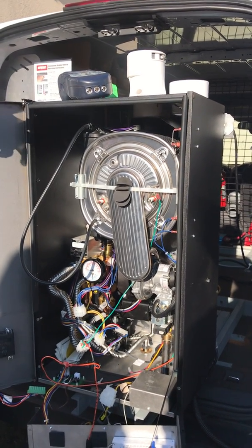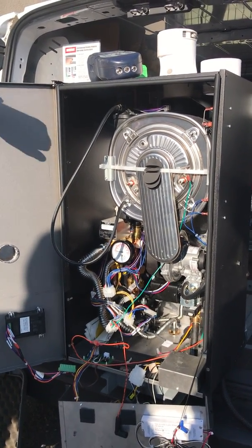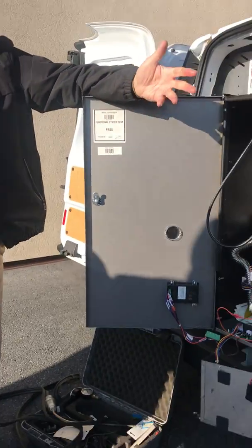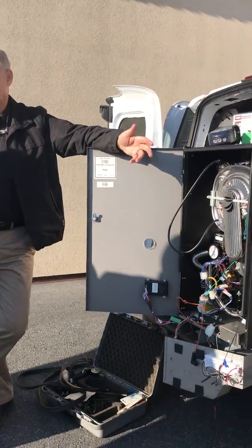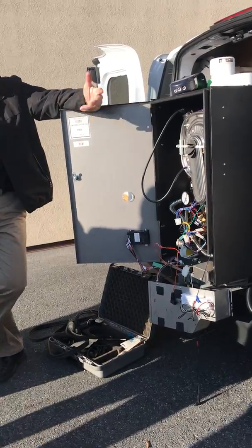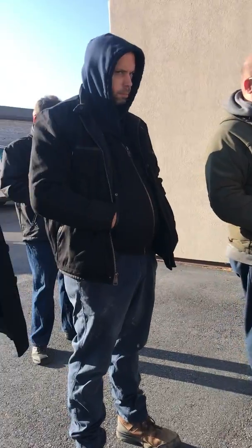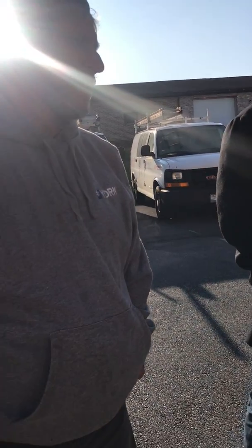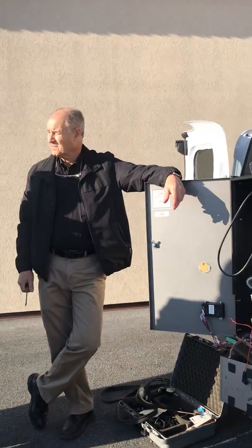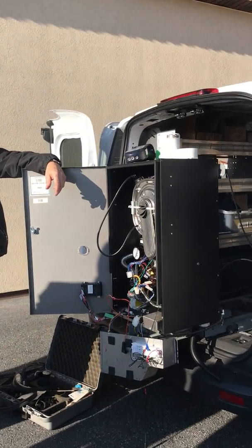I'm not saying you want to be changing heat exchangers. Right. But you can. I sold condensing boilers for a long time, and the ones I sold before, you couldn't change the heat exchanger. And a lot of those cracked too, didn't they? I got some of them that filled up, and a lot of them because they didn't put the Y strainers. They didn't put the stuff in there that we would use. Getting blockages more than anything. Yeah.